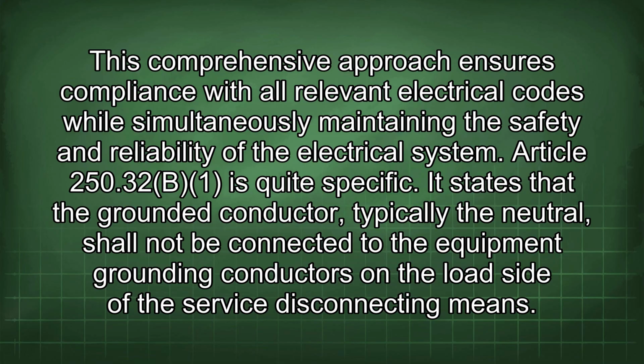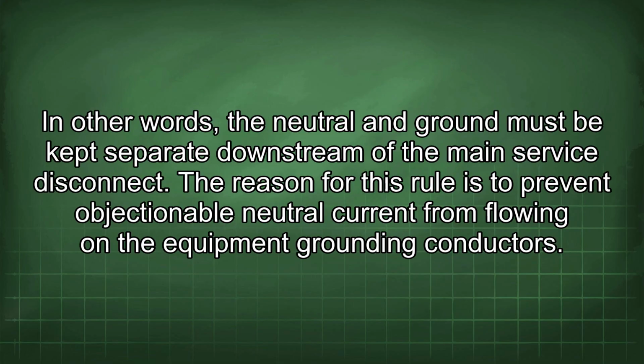Article 250.32 is quite specific. It states that the grounded conductor, typically the neutral, shall not be connected to the equipment grounding conductors on the load side of the service disconnecting means. In other words, the neutral and ground must be kept separate downstream of the main service disconnect.